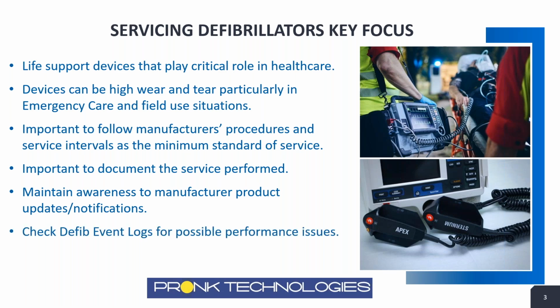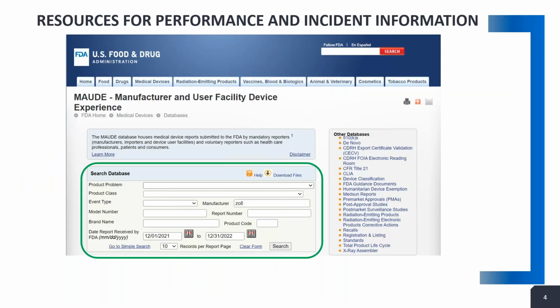And then, of course, we always want to make sure you're checking your event logs. It's a real common best practice on any kind of medical device. If there are event logs, particularly on a defibrillator analyzer, you want to be looking at those event logs for any common errors that could be causing a performance issue, maybe not today, but maybe in the future if you don't pay attention to it. So there's a database out there that's really available to all of us.